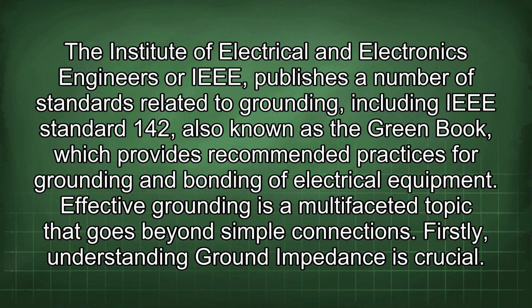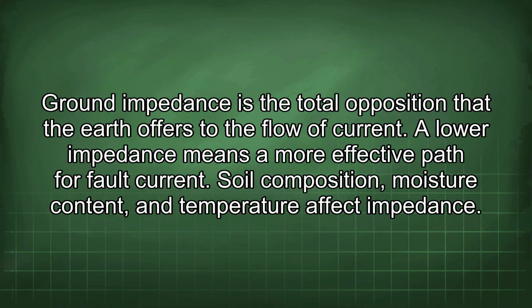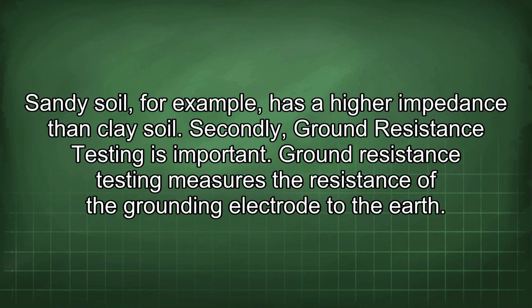Effective grounding is a multifaceted topic that goes beyond simple connections. Firstly, understanding ground impedance is crucial. Ground impedance is the total opposition that the earth offers to the flow of current. A lower impedance means a more effective path for fault current. Soil composition, moisture content, and temperature affect impedance. Sandy soil, for example, has a higher impedance than clay soil.